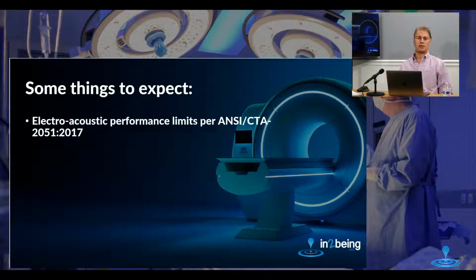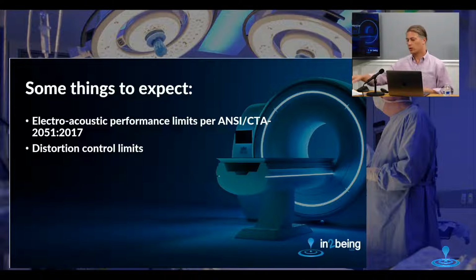Well, here are some things you should expect. Now, this is for the developers of over-the-counter hearing aid devices. This is just a brief overview of a couple of points that I know you're going to have to address. There's a lot more inside these 42 pages. If you ever want to crack it open, use the 2D barcode from earlier to go to the FDA website. Feel free to talk to us here at Into Being. But electroacoustic performance limits per this ANSI standard, they want distortion control limits.